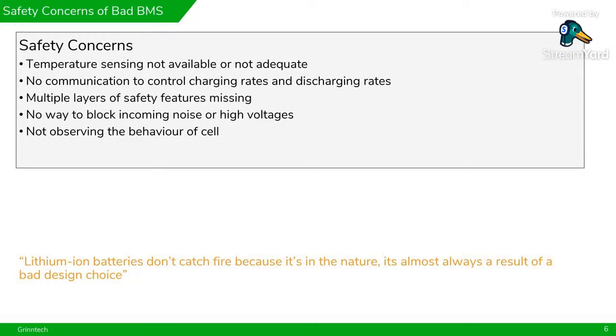These protection boards don't have multiple layers of safety, while a proper BMS will. For example, to avoid over voltage in a cell, a battery will typically have a minimum of three protection levels, sometimes four or five. First, when talking to the charger, you ask it to give only a certain voltage — that's the first protection level. Second, there's a TVS diode that behaves like a short circuit if excess voltage comes in — protection boards don't have this. Third, the BMS has settings that give a warning or can cut off — that's the third layer. There could be more, like a TVS diode on the charger itself, but none of that exists in a Chinese protection board.